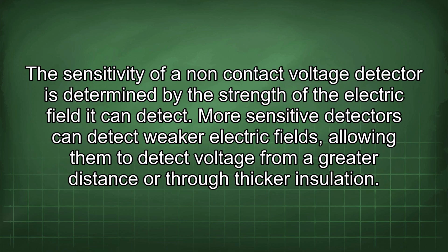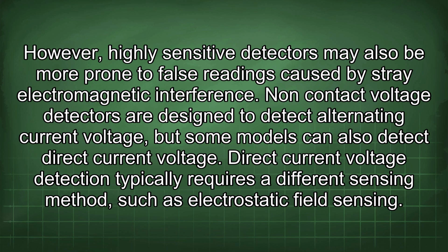The sensitivity of a non-contact voltage detector is determined by the strength of the electric field it can detect. More sensitive detectors can detect weaker electric fields, allowing them to detect voltage from a greater distance or through thicker insulation. However, highly sensitive detectors may also be more prone to false readings caused by stray electromagnetic interference. Non-contact voltage detectors are designed to detect alternating current voltage, but some models can also detect direct current voltage. Direct current voltage detection typically requires a different sensing method, such as electrostatic field sensing.